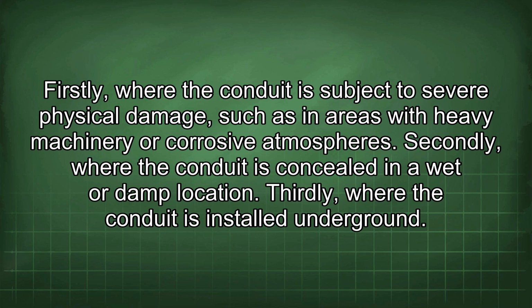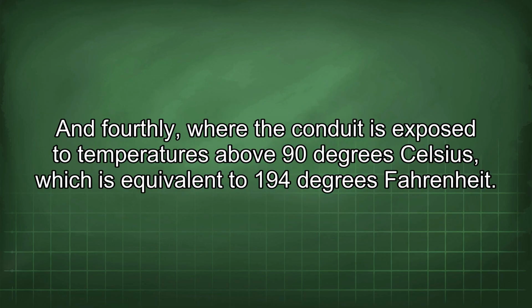Secondly, where the conduit is concealed in a wet or damp location. Thirdly, where the conduit is installed underground. And fourthly, where the conduit is exposed to temperatures above 90 degrees Celsius, which is equivalent to 194 degrees Fahrenheit.